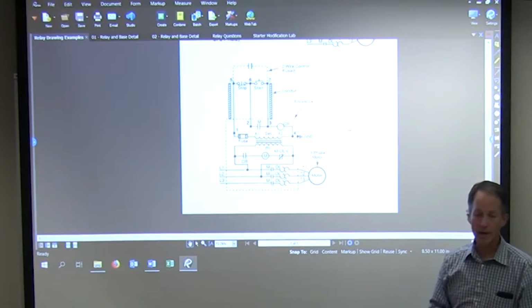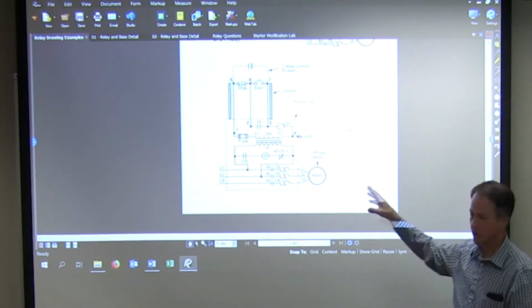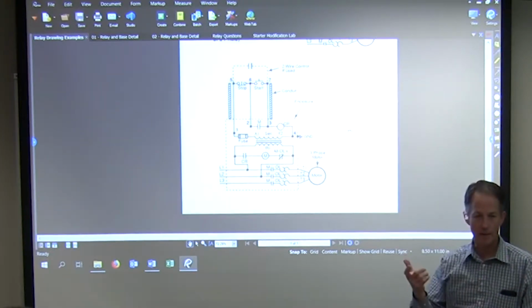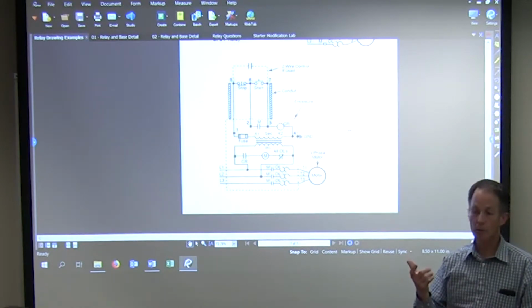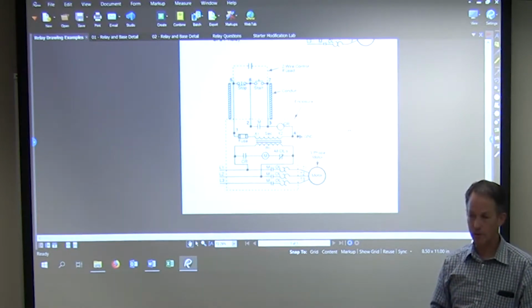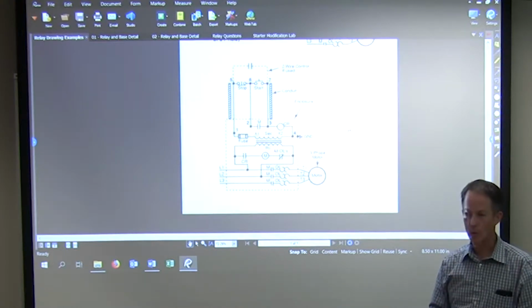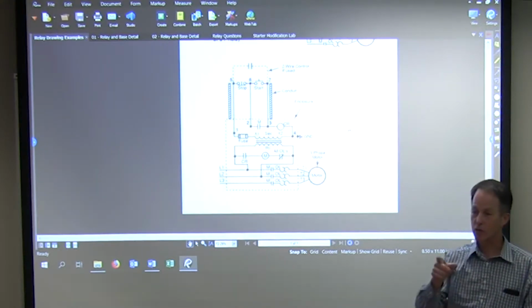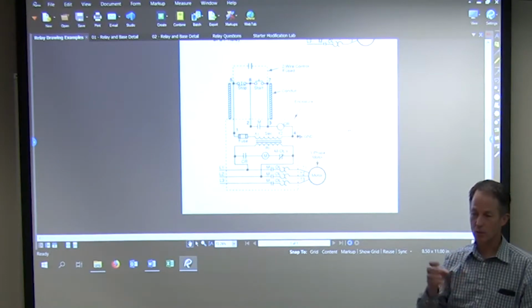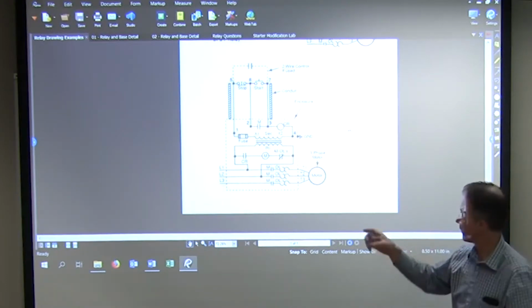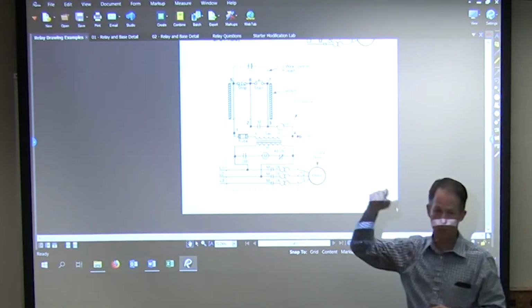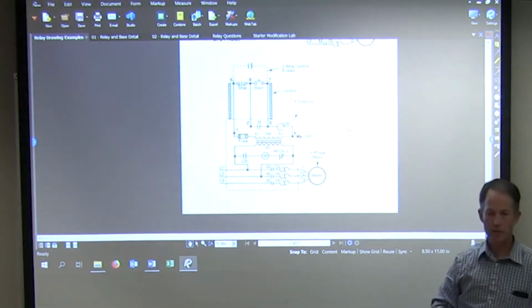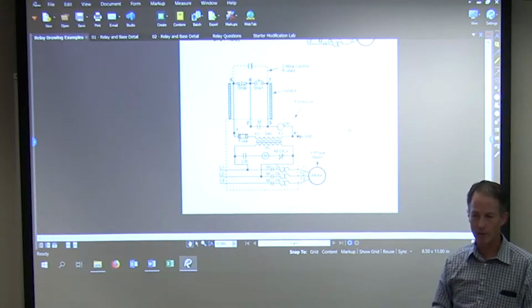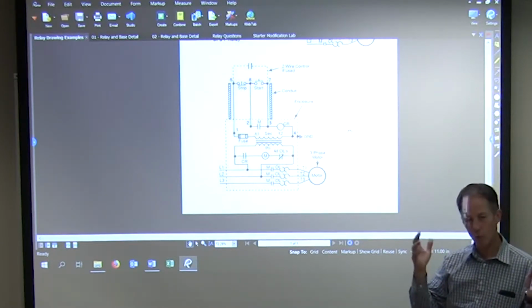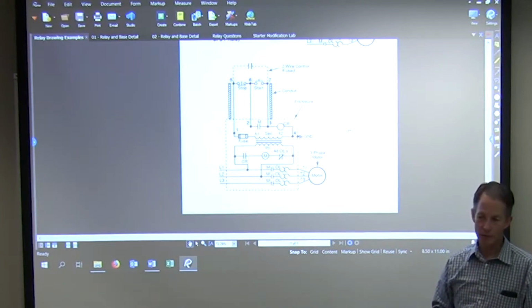Side story, we had a contactor and looked at this and thought, oh, I just have the coil of this contactor. That shouldn't be much. So we put in a 50 VA transformer. Guess what? It wouldn't work. It ended up chattering so badly that it actually ruined the core inside the windings. We had to replace it. So we got a bigger one, a 75 VA, or 100, I can't remember what it was. Still didn't work. Burned it up again. We ended up having to put in a 125 VA, 150 VA transformer.